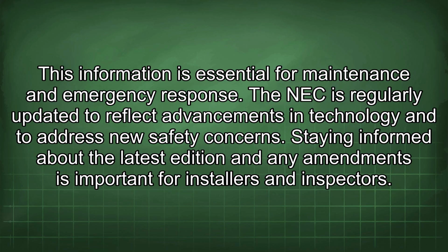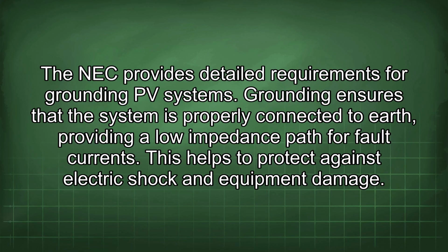The NEC is regularly updated to reflect advancements in technology and to address new safety concerns. Staying informed about the latest edition and any amendments is important for installers and inspectors. The NEC provides detailed requirements for grounding PV systems. Grounding ensures that the system is properly connected to earth, providing a low impedance path for fault currents. This helps to protect against electric shock and equipment damage.